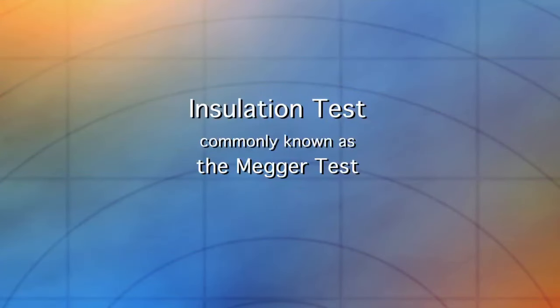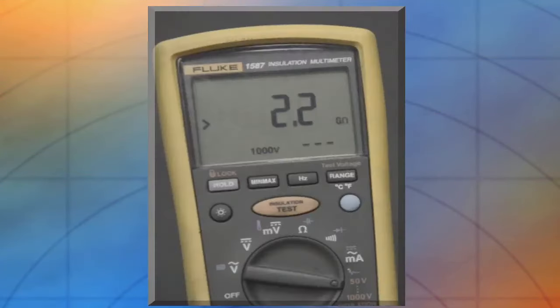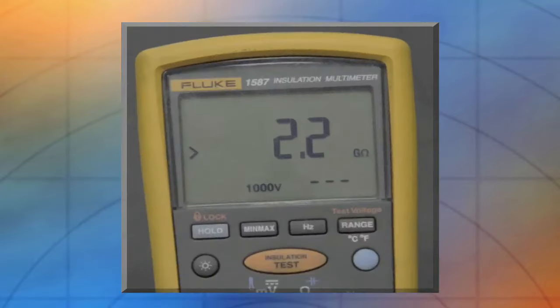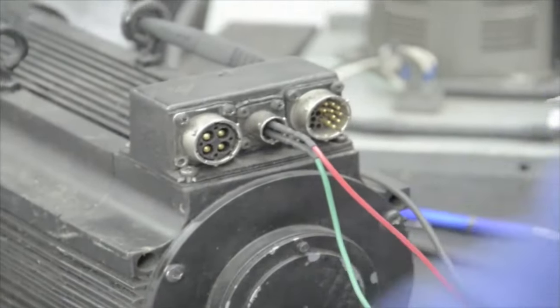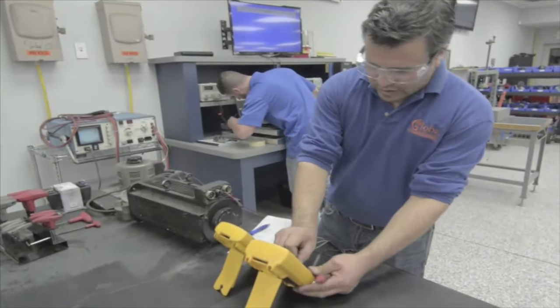Now, an insulation test, commonly known as a Megger test, using an insulation multimeter is being performed. We first connect one lead to ground and check through each phase to ensure that the windings are not grounded or that the insulation is not broken down.